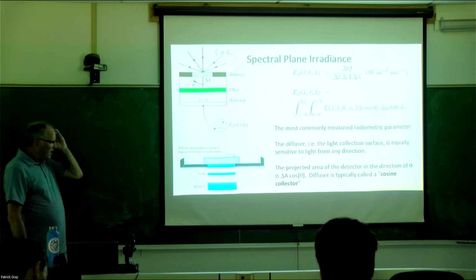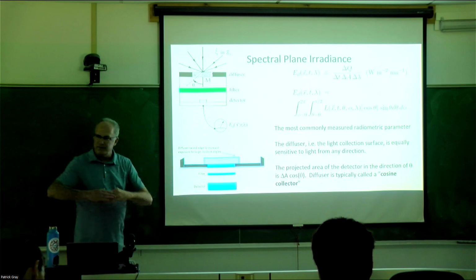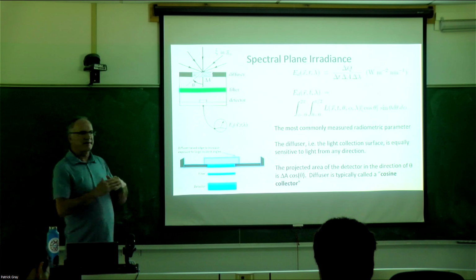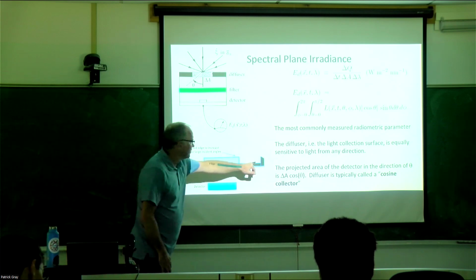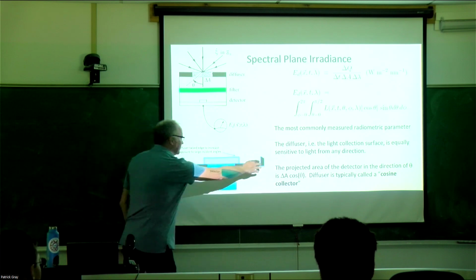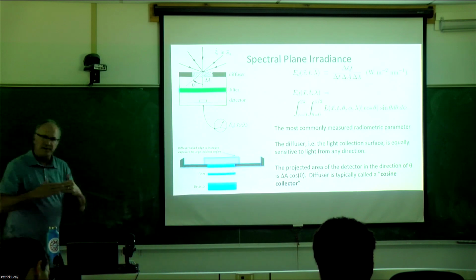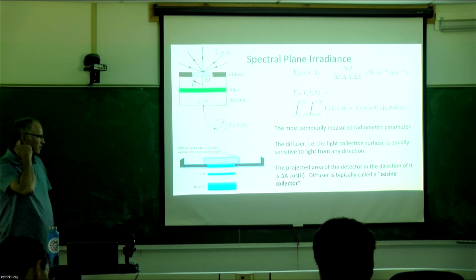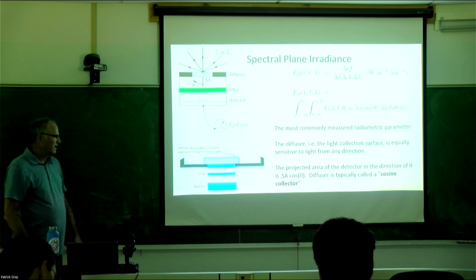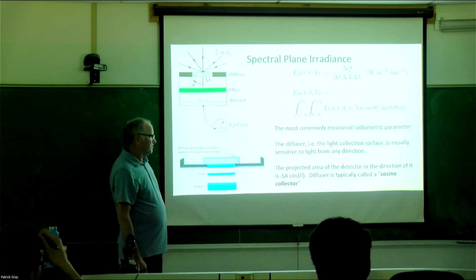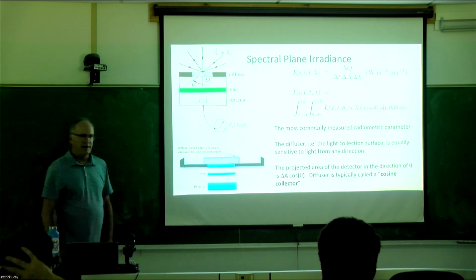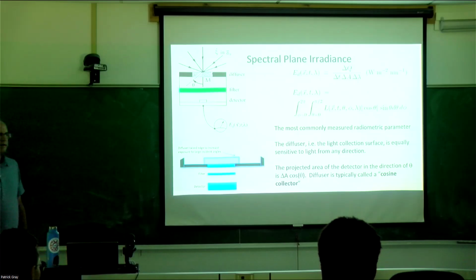Notice that with most radiometers, we have to get rid of some edge effects, out of band stuff coming from different steep angles. So we put them in a little shallow well with some sort of baffles on the edge, to keep everything measuring the downwelling plane, the filter and detector. Now, the important part of this diffuser is it has to match what's called a cosine response.